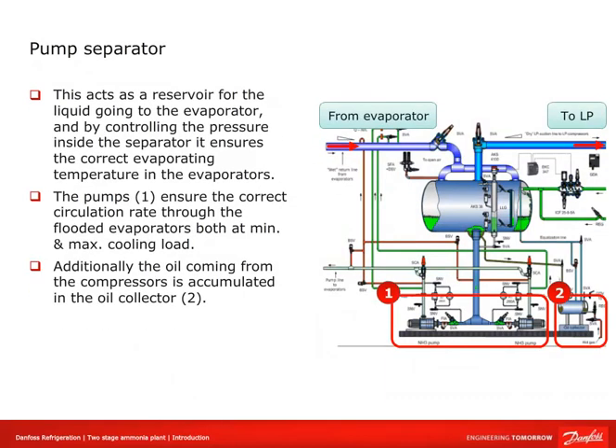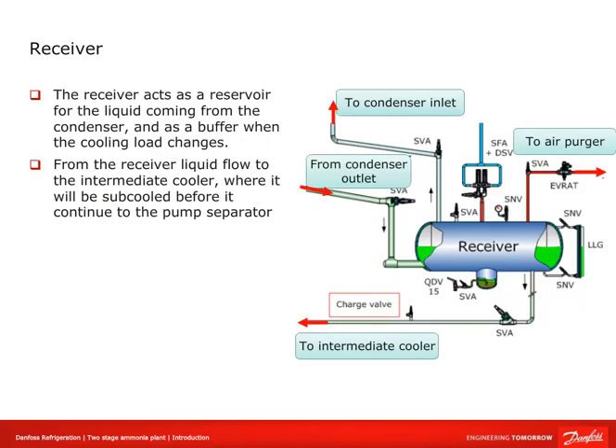The pump separator acts as a reservoir for the liquid going to the evaporators. By controlling the pressure inside the separator, it ensures the correct evaporating temperature. The pumps ensure the correct circulation rate through the flooded evaporators at both minimum and maximum cooling load. Additionally, oil from the compressors accumulates in the oil collector. The receiver acts as a reservoir for liquid coming from the condenser and as a buffer when cooling load changes. From the receiver, liquid flows to the intermediate cooler where it is sub-cooled before continuing to the pump separator.